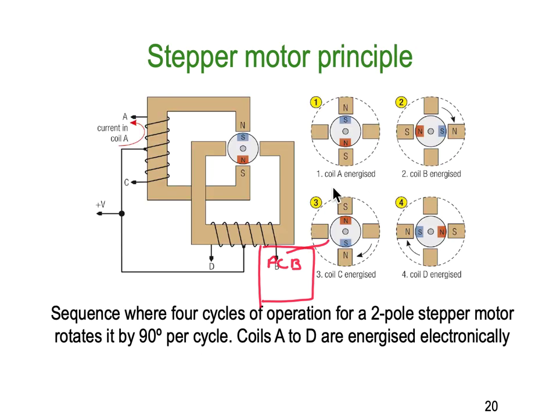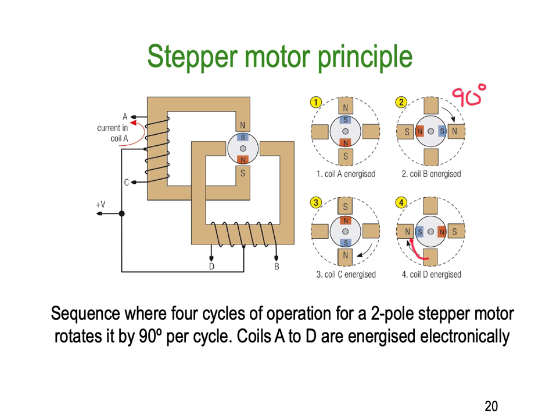This is how the stepper motor actually works. In step one we set up a north and a south. Step two we simply move the north and the south around — in this case 90 degrees, so our stepper motor would step 90 degrees per switch rather than 7.5 degrees like the previous example. In the next switch we've moved it around another 90 degrees, and so on. Effectively all we're doing is putting the appropriate current through the appropriate winding to simply step the motor around 90 degrees at a time.